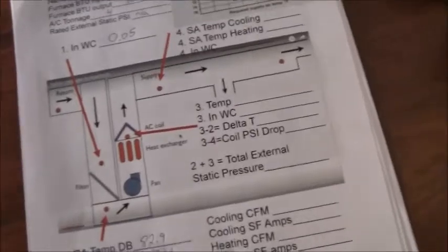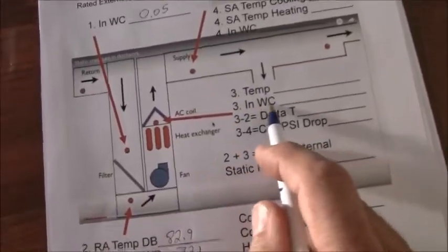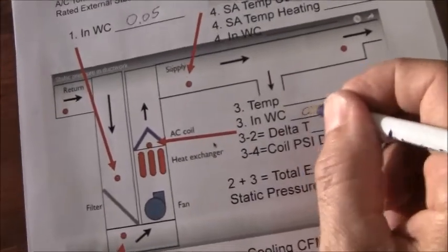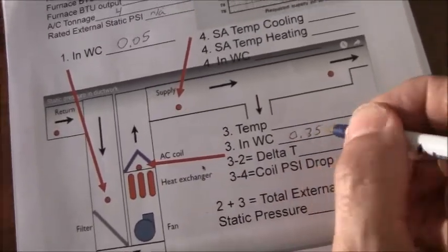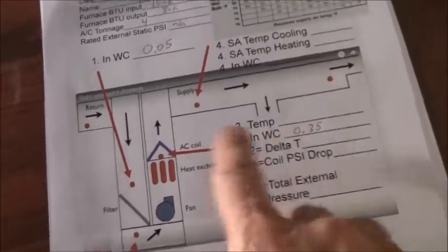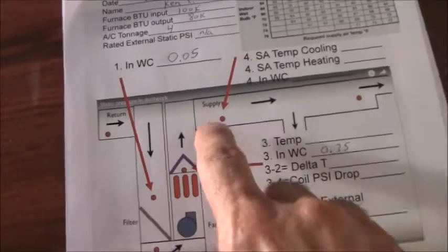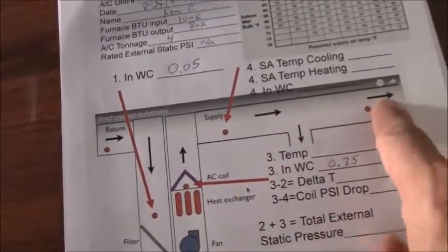Okay, so that number 0.35 goes right here. That's that number right there. Now we need another number. This number right here after the coil where it goes into the plenum. Now, here's the coil. This sample point here is before the coil. Now, I took out a screw right there, and that is where we're going to go after the coil, and it goes into the plenum. Could be anywhere up there, but since there was a screw right there, it was just easy for me to remove that screw and use that as my sampling point.